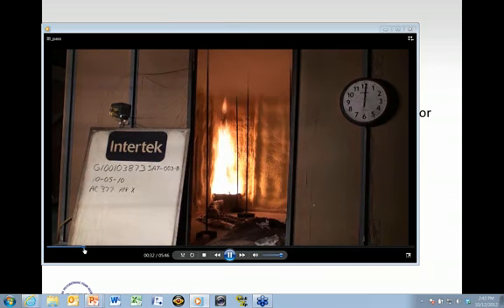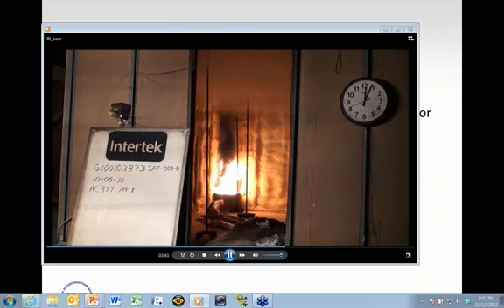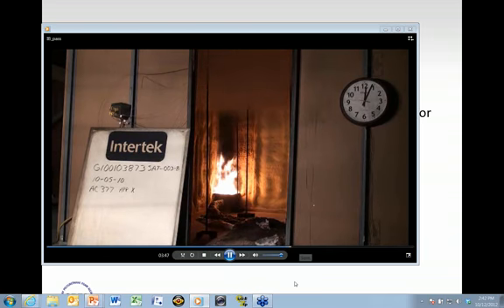I'm not going to go through the whole 4 minutes and 18 seconds. I'll give you a quick snapshot here. You see we're about 2 minutes into the test, and really nothing is happening. We see some smoke in the room, but really no flame spread. So we move ahead a little bit. We see in about 4 minutes, nothing happening. And we'll see soon here in about 4 minutes and 18 seconds, again, nothing happens. Here we are, 4 minutes and 18 seconds. This particular coating passes for an ignition barrier coating. Right now, it passed 4:18.